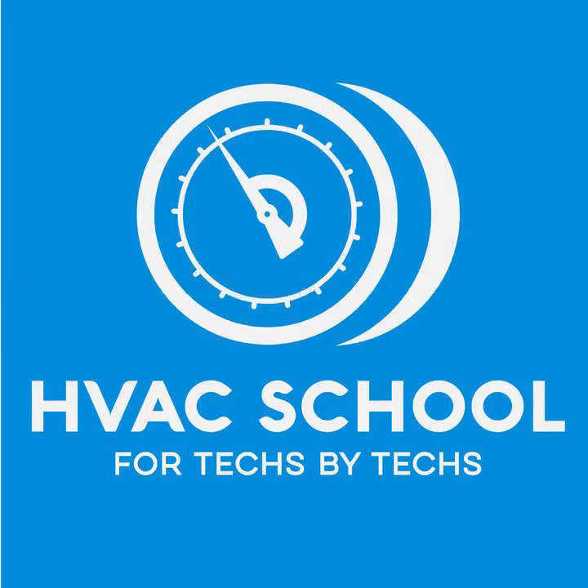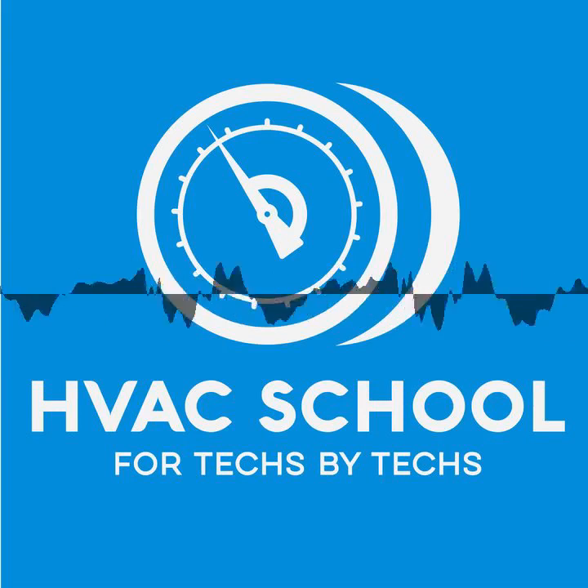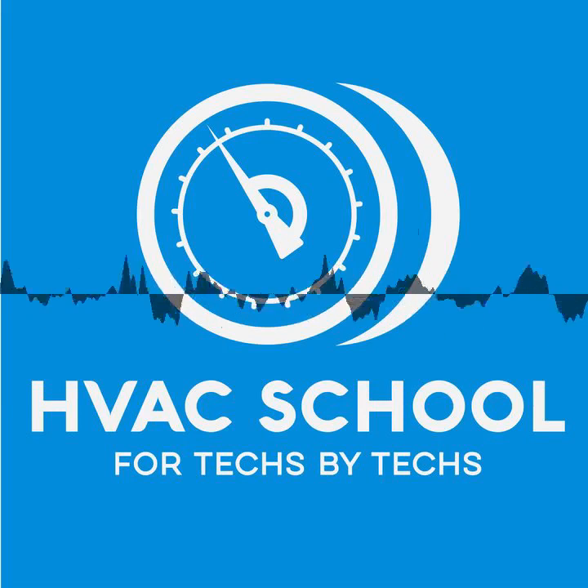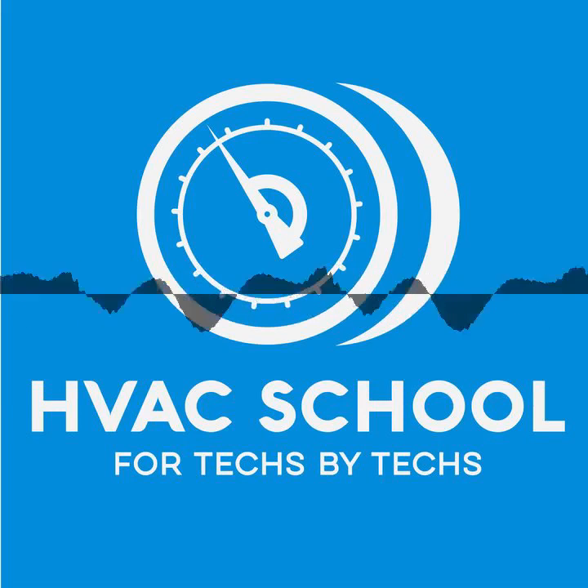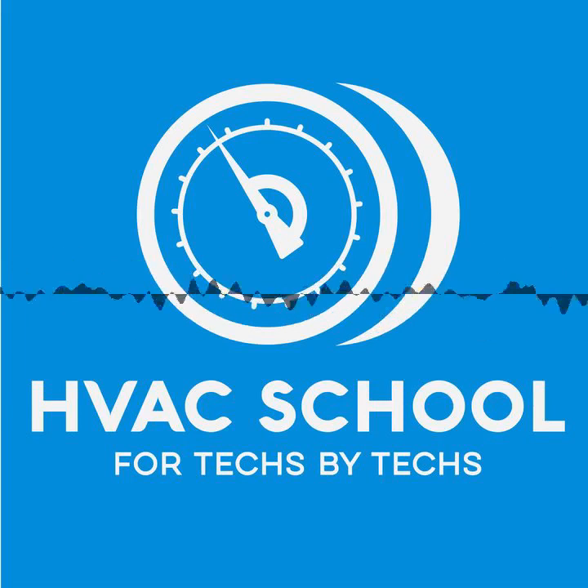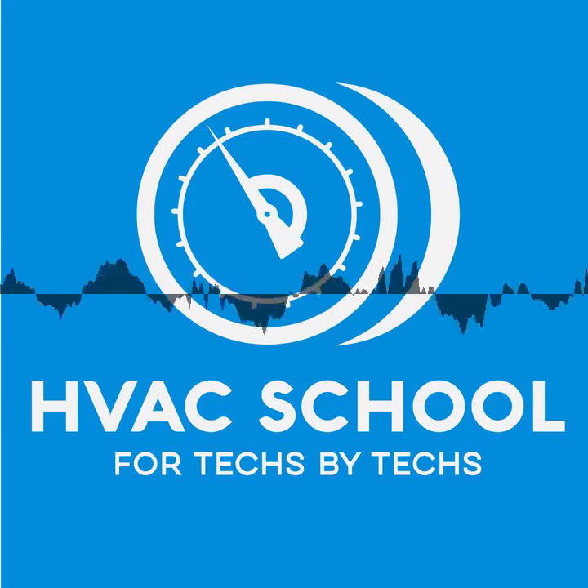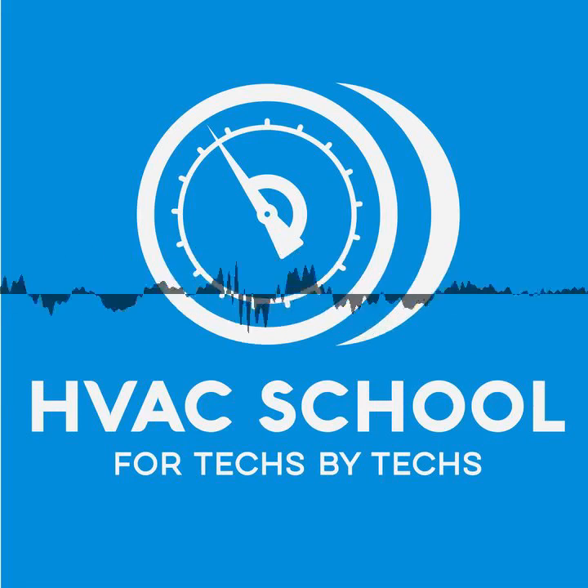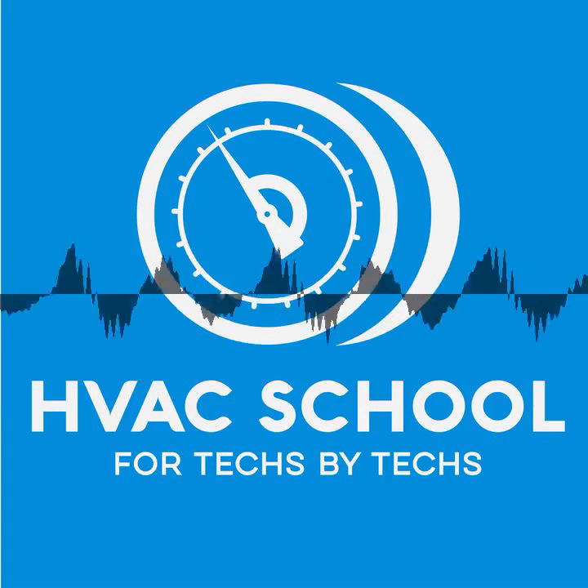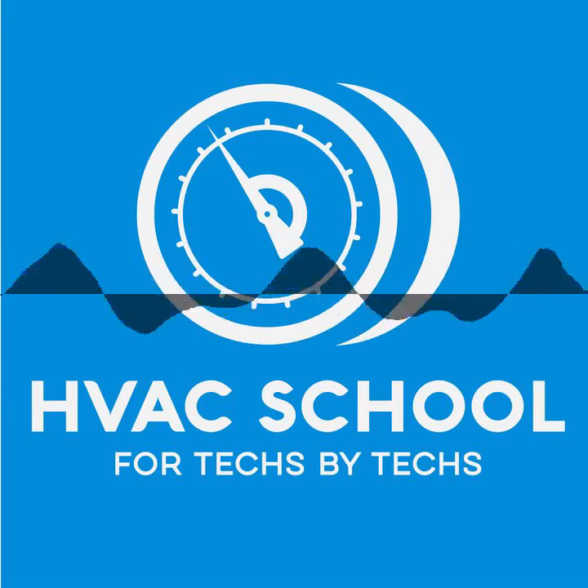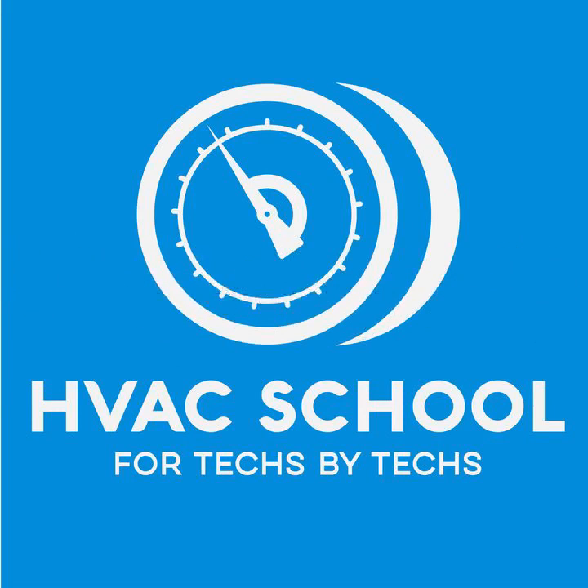But here's the catch. If you happen to have a smart thermostat, it should have algorithms that say, look, if we drop our humidity in our space 10%, we can bump our dry bulb temperature up a couple of degrees so that it still feels the same comfort level that it would have been if it was 2 or 3 degrees cooler, but had a higher humidity level. You see what I'm saying here? The human experience is the same either way as far as your body is concerned. By keeping the space a few degrees higher and pulling more moisture out and keeping the relative humidity lower, we achieve the same comfort level without really using more energy.